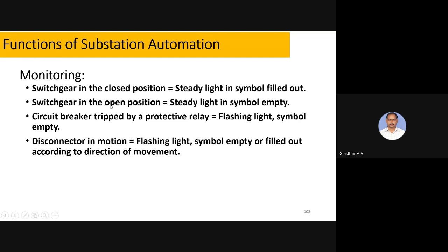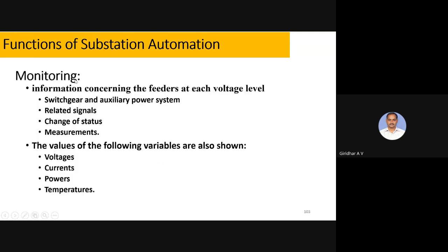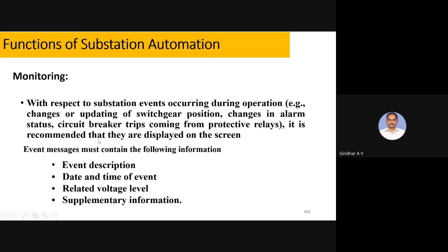So these are the displays that will be there, with lights for the closed and open positions. If any circuit breaker is tripped by a protective relay, there are flashing lights like that. Those types of displays will be easily understood and necessary actions will be taken. So information concerning the feeders, switchgear, auxiliary power system, related signals, change of status, and measurements of voltages, currents, power, and temperature. In these monitoring aspects, the event date and time stamping, all that information, and appropriate alarms can be given at appropriate times.